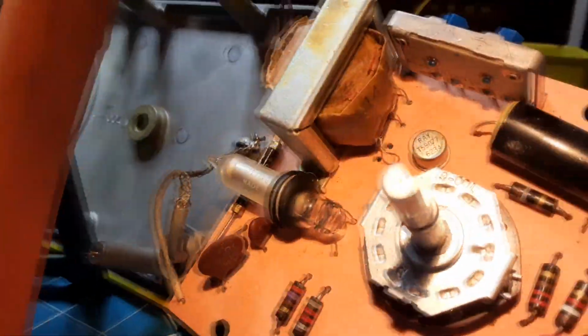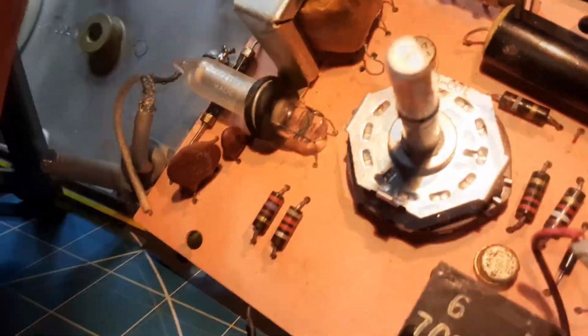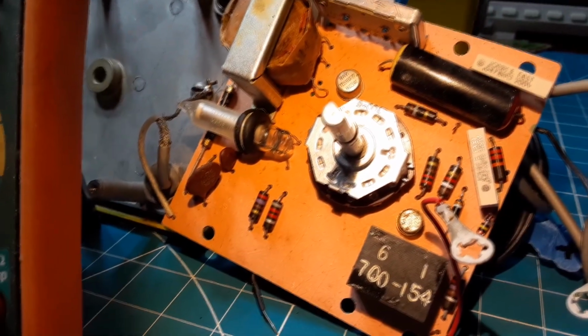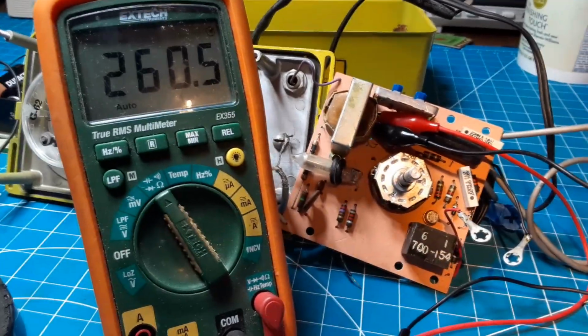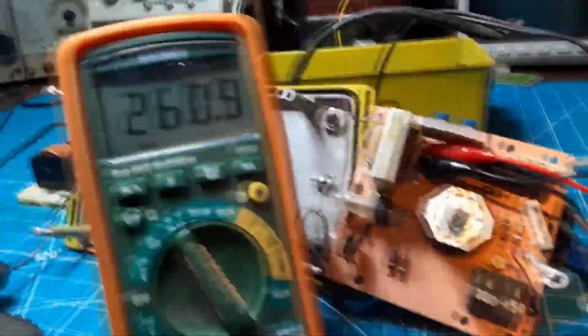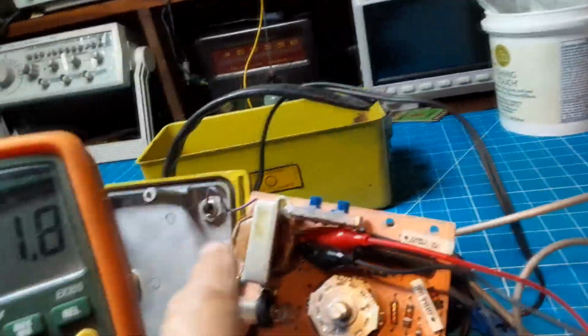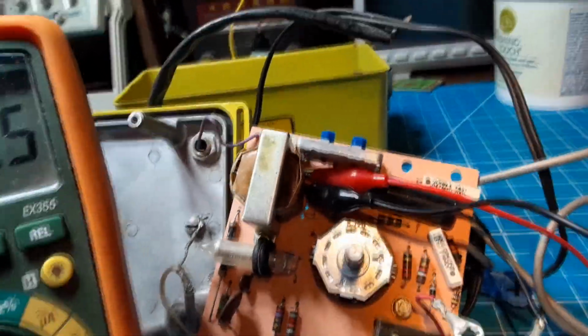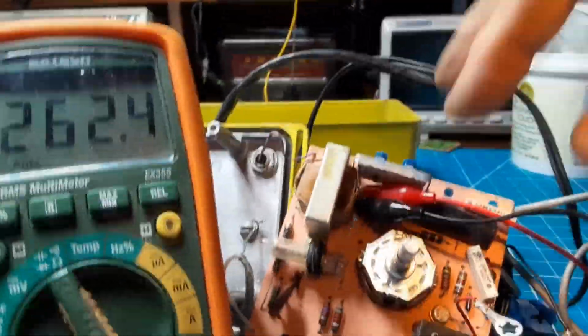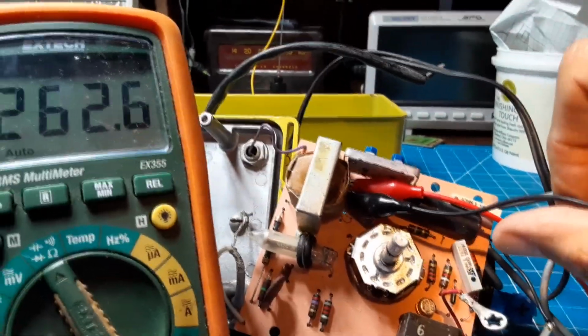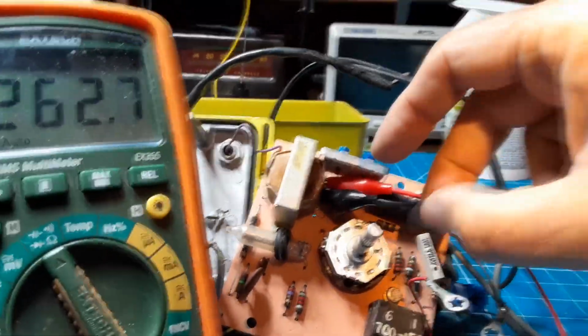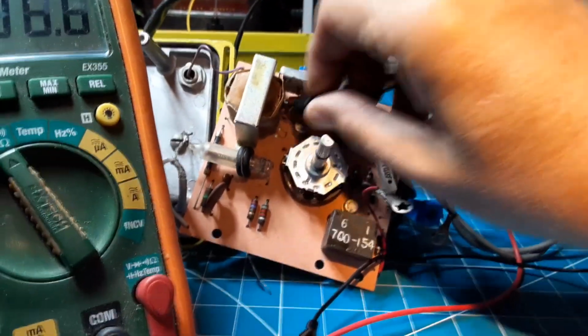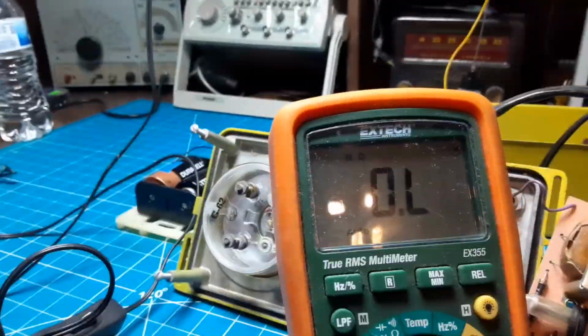Let me set up my little, and give me a second to hook up these alligator clips. Okay, so you see I'm across those two. I got 260 ohms, and I was wrong saying that that's the input. That's actually the output. I'm used to seeing two wires on an input on a transformer, right, and a center tap output. But in this case, there's two sections in, and they switch over. They reverse in the schematic, which we've seen. So we got 261 ohms there, so we're okay there. If I go to here, we got an open load.